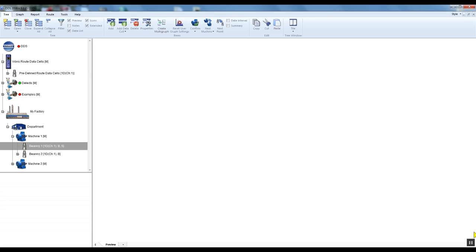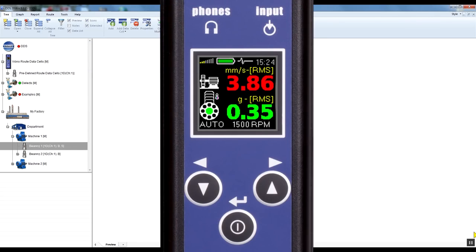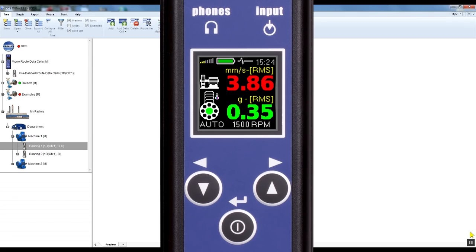Let's take a look at the first Vibrio M screen. We can see velocity RMS in millimeters per second or inches per second in the 10 to 1000 Hertz range, and acceleration in G in the 500 Hertz to 16 kilohertz range.